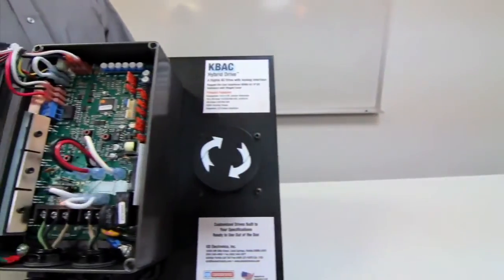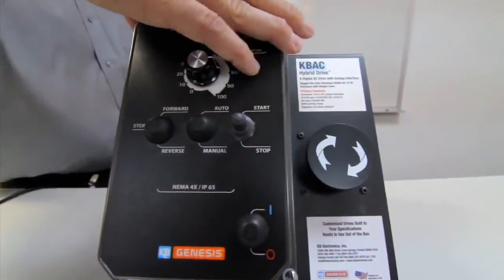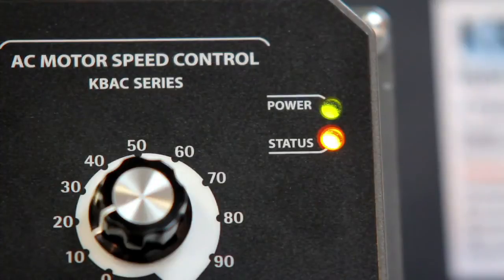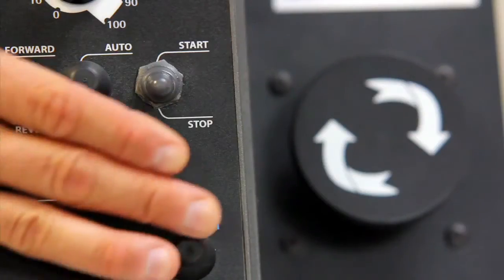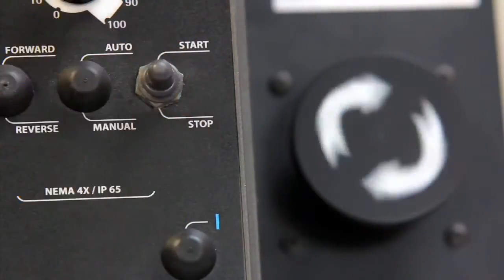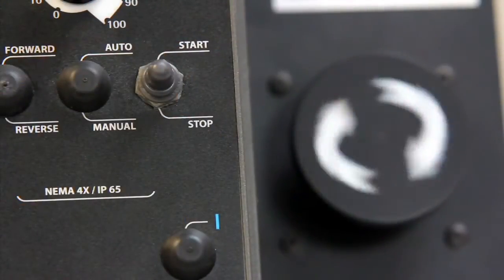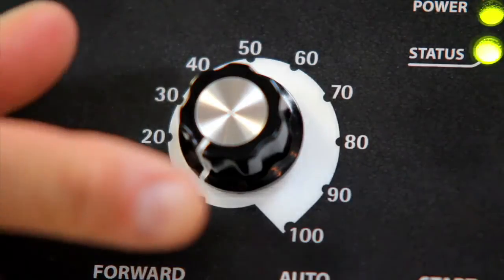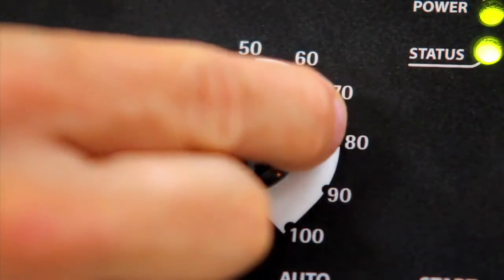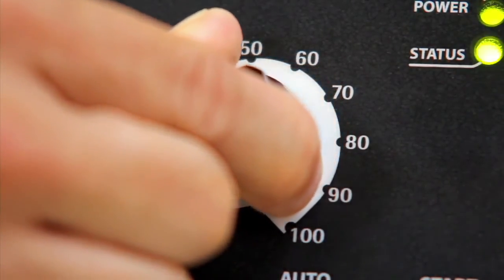Close the cover and power the drive. The status LED light should be yellow and the power LED light should be green. Push the start-stop switch and release. The status light will start blinking green. Begin to increase the speed of the motor by turning the main speed pot clockwise.